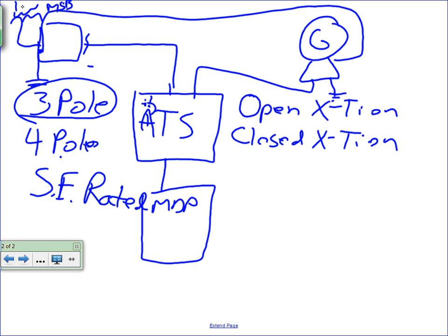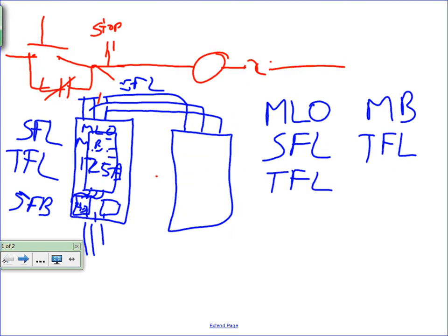There's also your short circuit current rating, which could dictate which panel we use. I should have covered that, it's something I did not cover. There's fully rated panels. Have you guys heard of series rated panels? Okay, and these NQ panels, which is our 208, we can fully rate up to 22,000 amps of fault current, okay? But we can series rate it up to 65, even higher, depending on what the main breaker is. What we're actually doing with a series rating is, the main breaker in the panel, or at least the breaker upstream that's feeding that panel, we've actually tested the combination of that breaker and these breakers that are in this panel board, right?